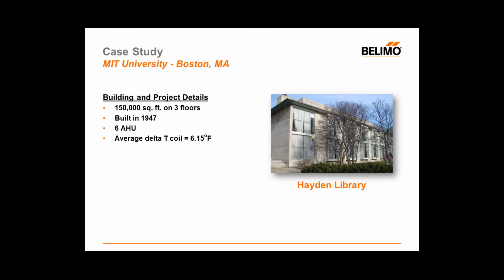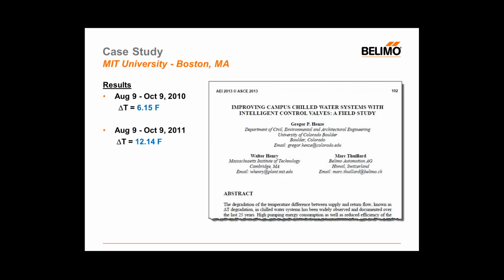But obviously, or maybe not obviously, but factually, they did not pull all of the 6-degree coils out of all of the air handlers, and so they wound up having some difficulty matching a 12-degree chiller with some 6-degree coils. So basically, it had very large coils, taking a lot of water to create the cooling, and the energy valve was put into place to see if we could slow that water down and demand higher delta T and still satisfy the spaces. So we had a great success there.